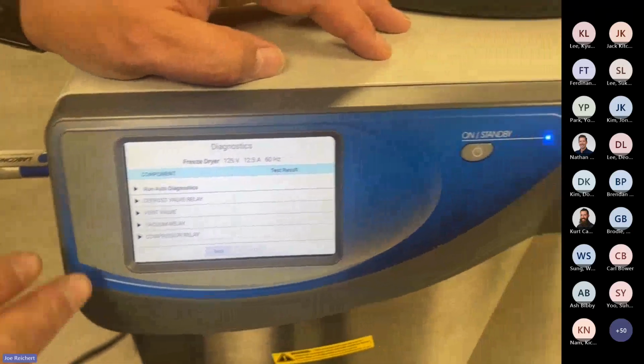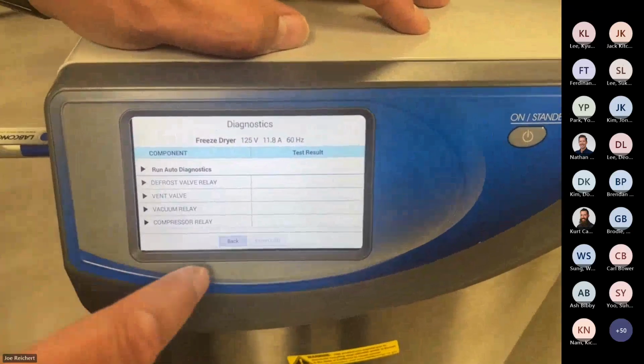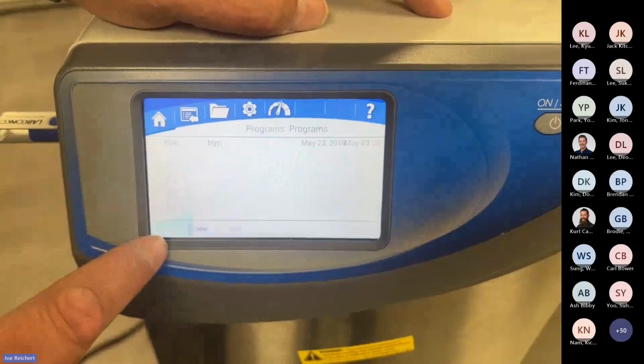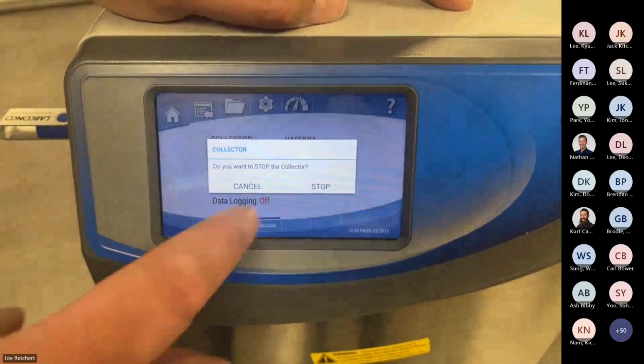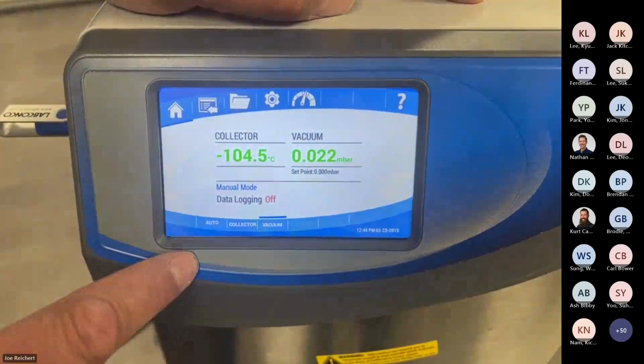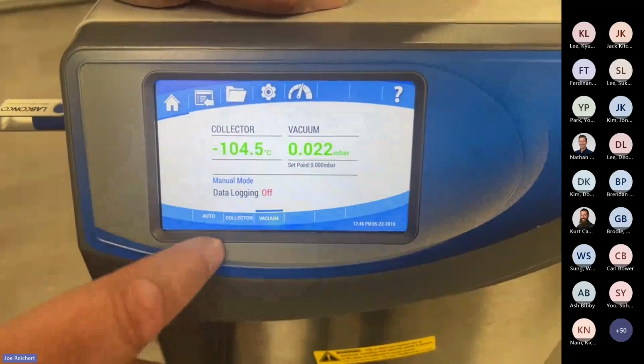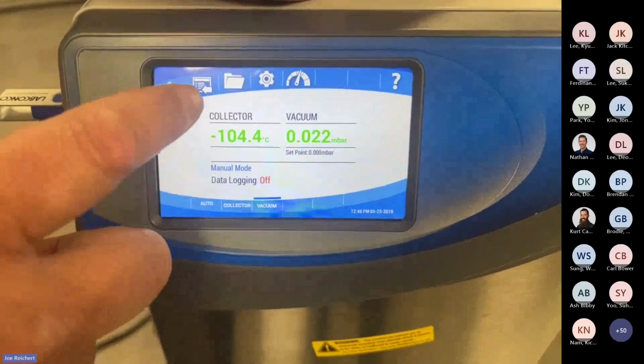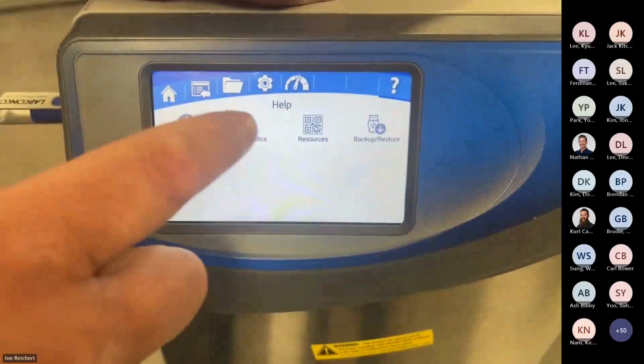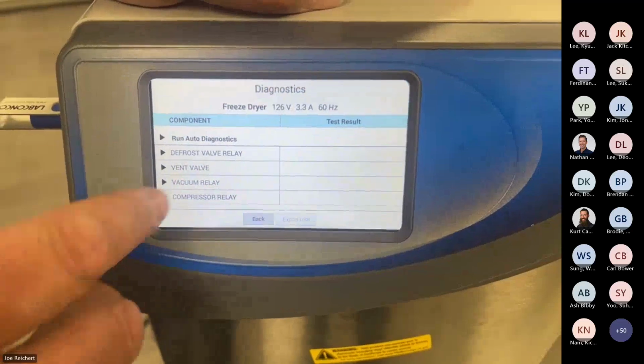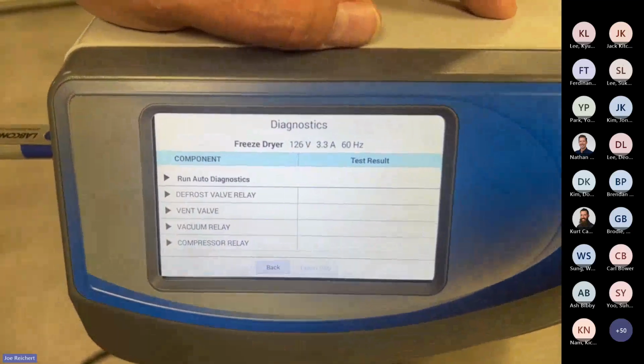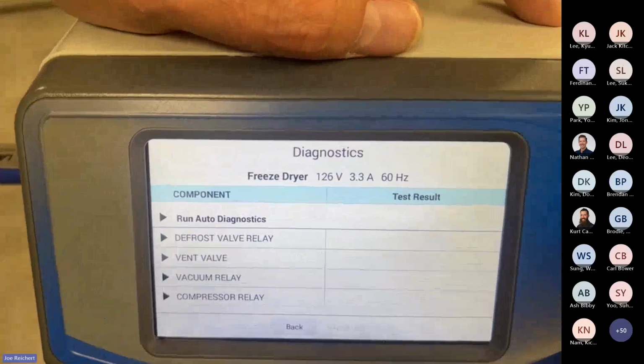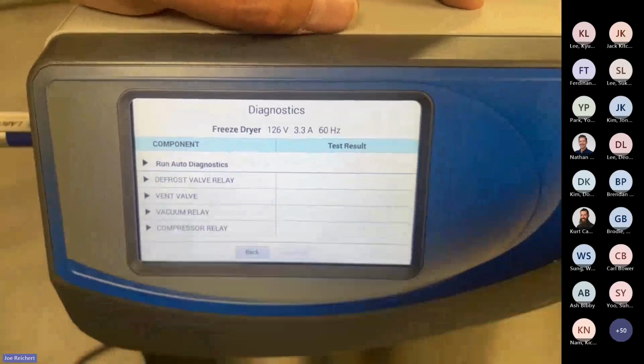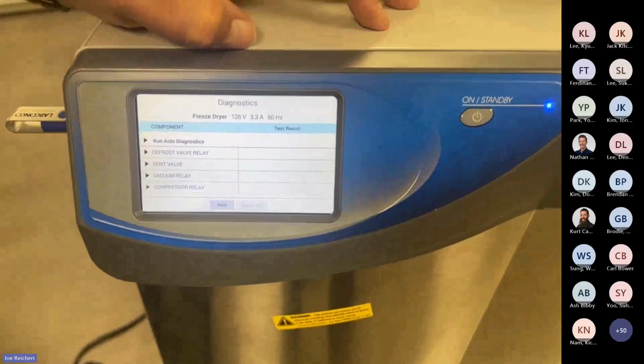You can always go and just turn on your vacuum pump. Like if I turn off the refrigeration, stop that, and then if I go back to the diagnostics mode, now it shows me that I'm only pulling 3.3 amps. I have a scroll pump connected to this unit right now, and so they don't run at very high amperage.